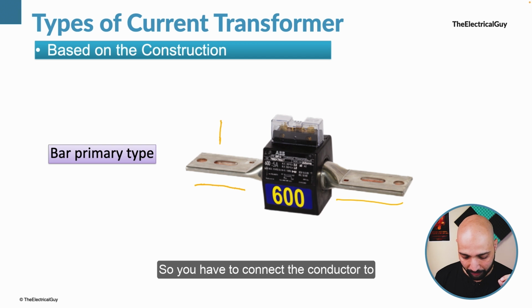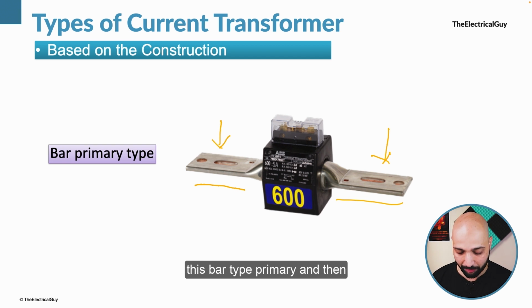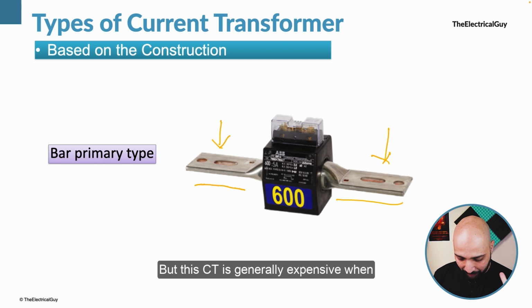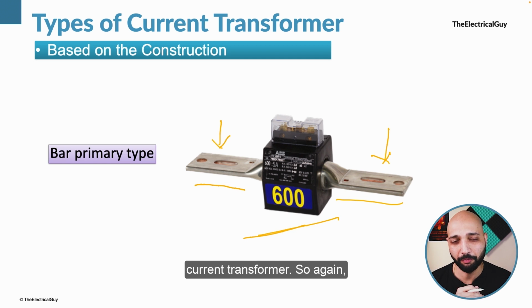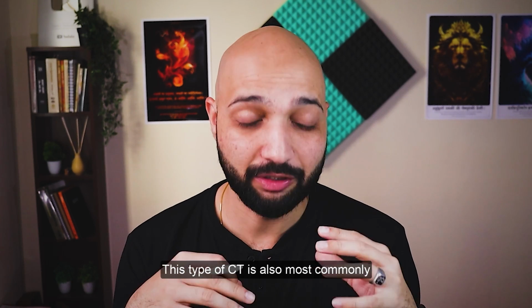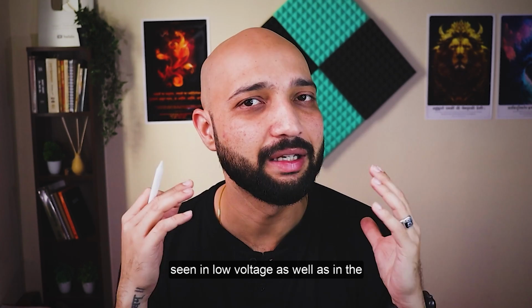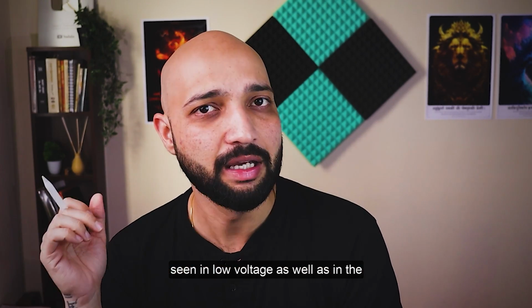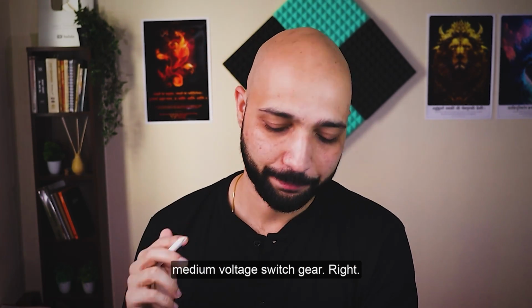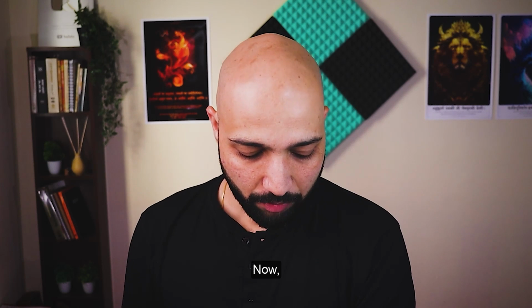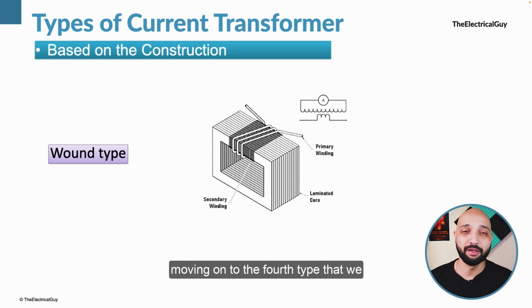So you have to connect the conductor to this bar type primary and then measure the current, right? But this CT is generally expensive when we compare it with the window type current transformer. So again, it depends upon the requirement. This type of CT is also most commonly seen in low voltage as well as in the medium voltage switchgear, right? Now, moving on to the fourth type that we have here is the wound type current transformer.